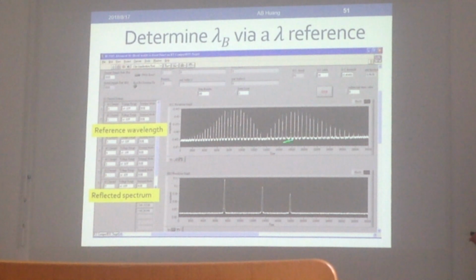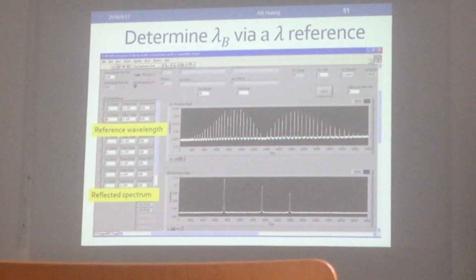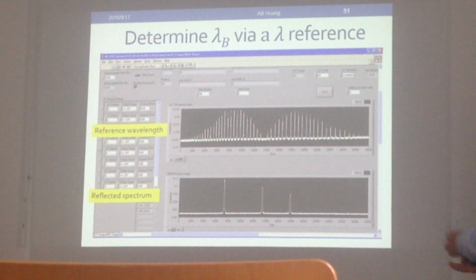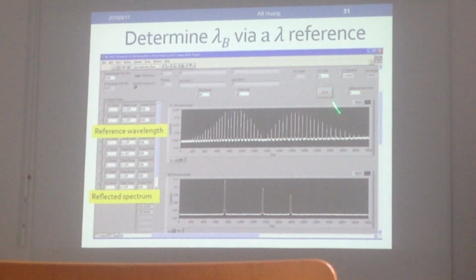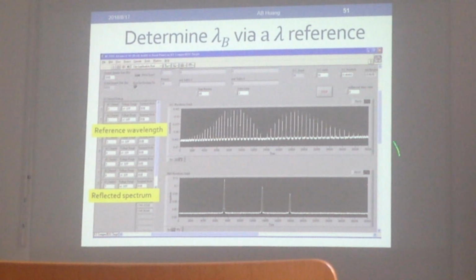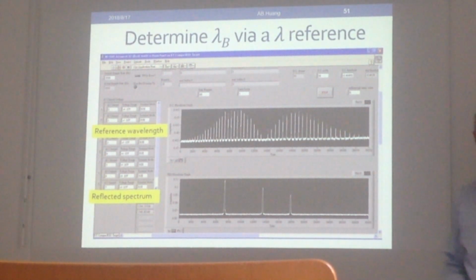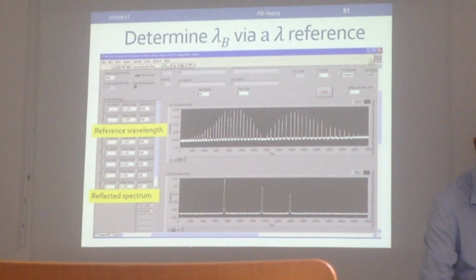So then the sequence numbers are the same here and there. Whatever this sequence is, you look in here and check its wavelengths and use the peak value to interpolate the wavelengths. The important thing is this reference wavelength does not shift with time, does not change as the light intensity becomes weaker, does not change when the optical fiber becomes old. This is why FBG readings do not drift. Electrical sensors, most of them, tend to have zero shift or drifting of the readings. The FBG does not. Extremely stable. This is a very important reason why FBG is good for long-term measurement.